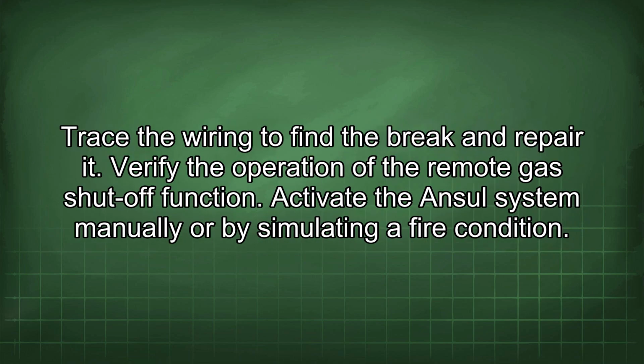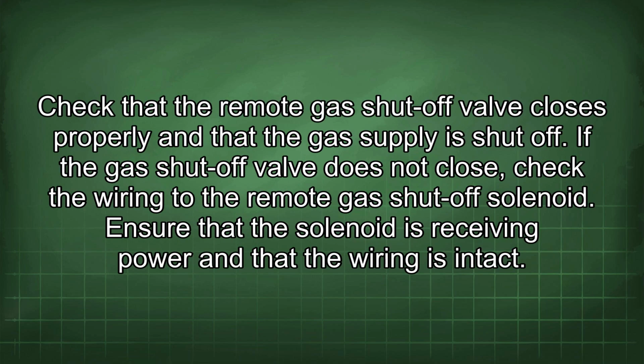Trace the wiring to find the break and repair it. Verify the operation of the remote gas shut-off function. Activate the Ansul system manually or by simulating a fire condition. Check that the remote gas shut-off valve closes properly and that the gas supply is shut off.